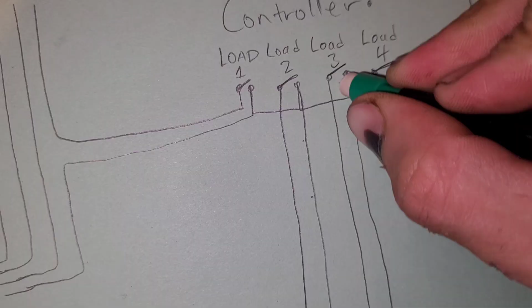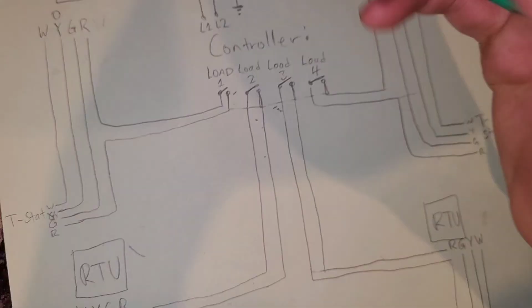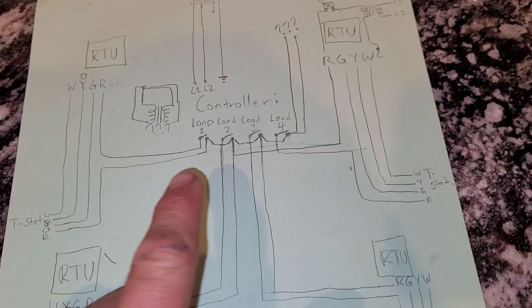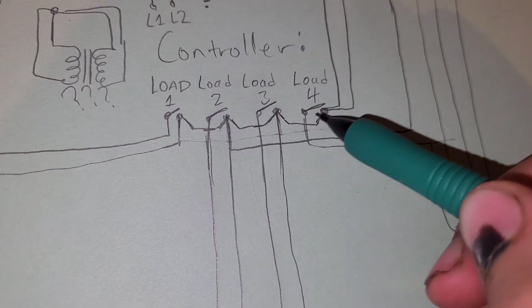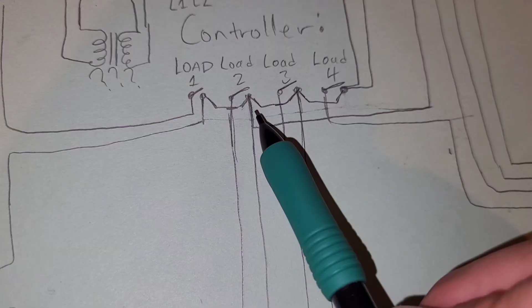So of course we got rid of these connections between the common side of stuff, isolated the pairs to what they were actually supposed to be to, and hooked it up like this. So I looked back, and this is actually exactly how they had it wired. So they had the jumpers between the commons like that, and then the R that was supposed to land here on load 4 they had brought over to load 2 and just tied in there for some reason.